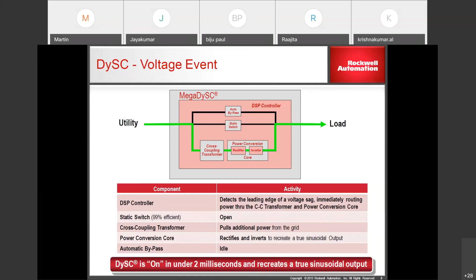Automatic bypass is on. Now, when you look at the turnaround time, DySC is on under 2 milliseconds and recreates a true sinusoidal wave. The 2 milliseconds can be further split: 0.3 millisecond is for the detection and 1.2 to 1.3 milliseconds is for the restoration of voltage to the true sinusoidal level. So with that, the overall turnaround time of the DySC device under the voltage sag event is accounted under 2 milliseconds.